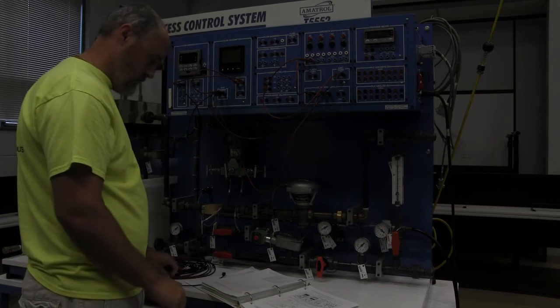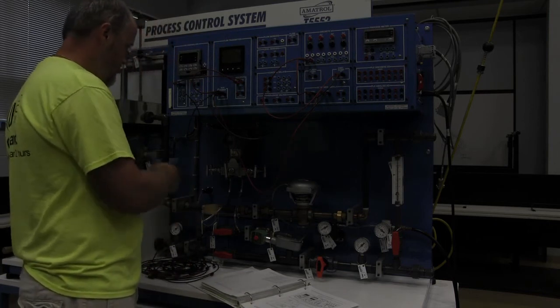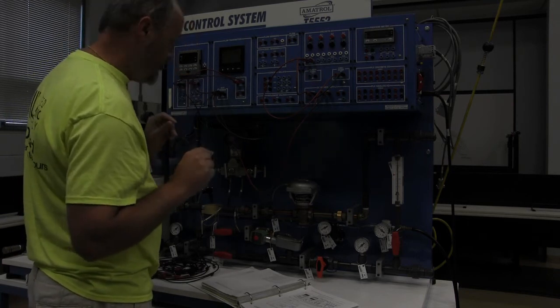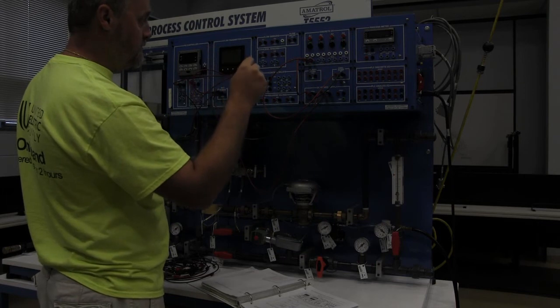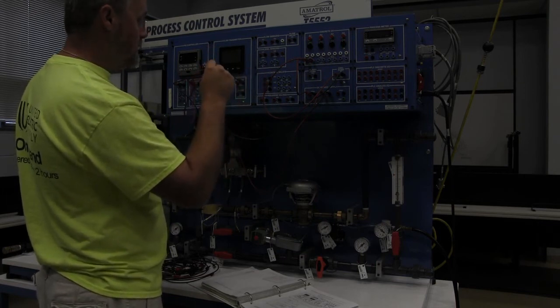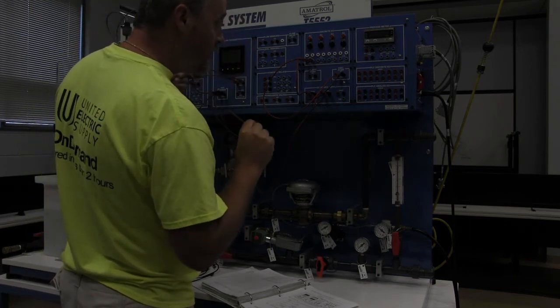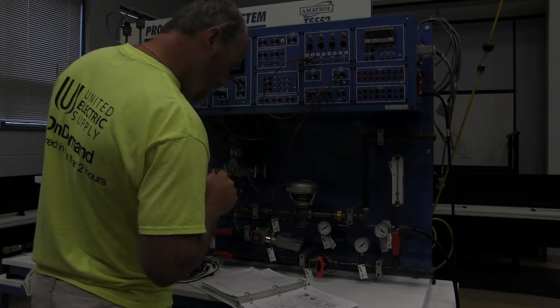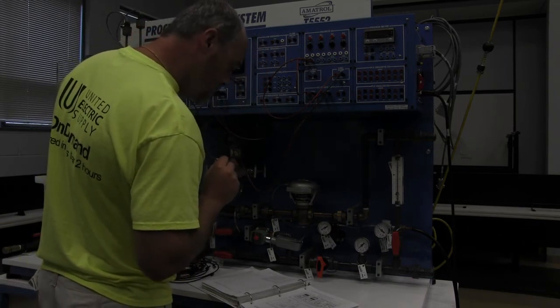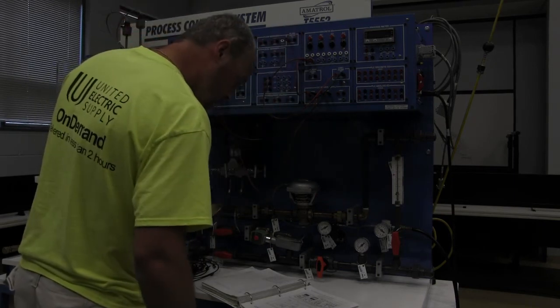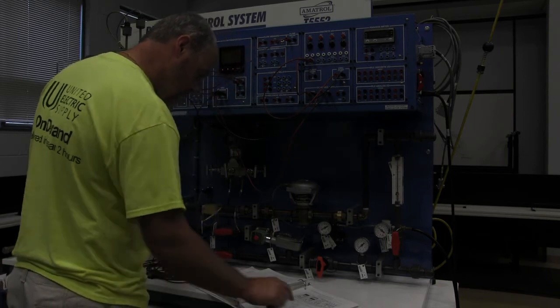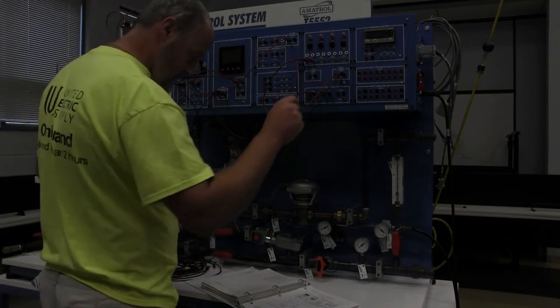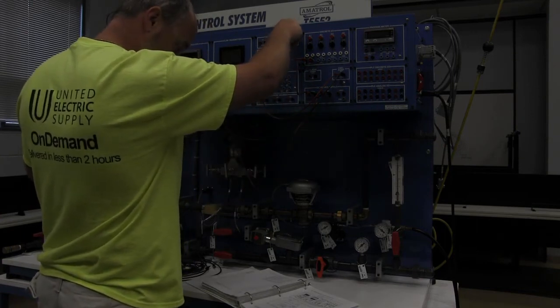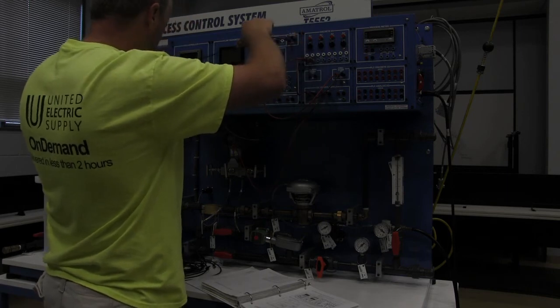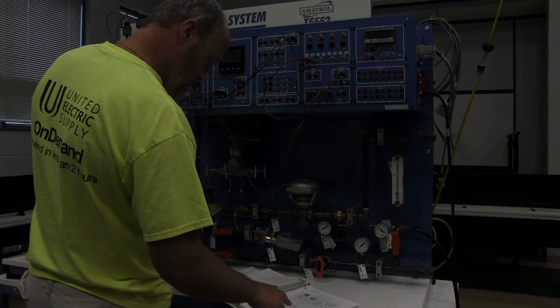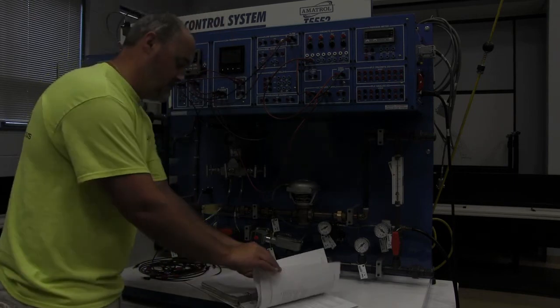And then the controller analog output over to the IP converter, which is, let's see here, flow valve. Yeah, FV1. And then we're coming off the negative of that and going back to the negative here. The positive over to the positive, and the negative to the negative. All right, so that's wired as shown.